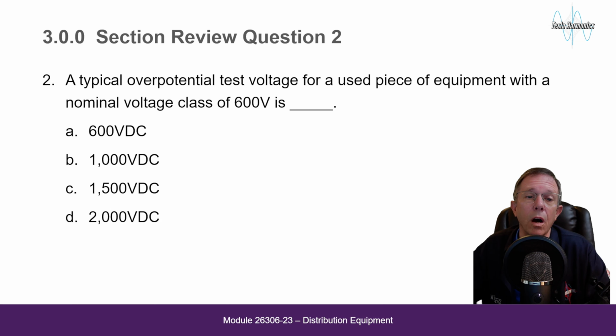A typical overpotential test voltage for a used piece of equipment with a nominal voltage class of 600 volts is 600 volts DC, 1000 volts DC, 1500 volts DC, or 2000 volts DC. That's going to be D, 2000 volts DC.